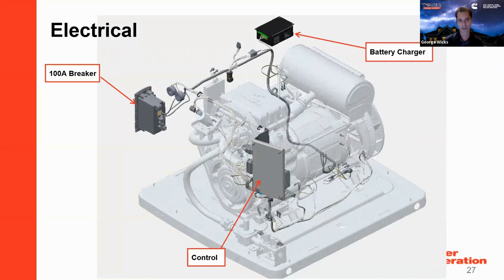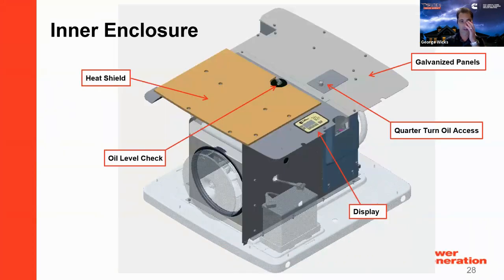In the standby gen lineup, they all come with a 100 amp breaker and a battery charger built into the generator. Different from Generac, we need a 120 volt circuit run out to our unit. Without that, the battery charger won't power and backfeed the battery, and within a month or two, the generator battery will be dead. That's one of the things installers are used to dealing with. Other brands that don't have these features onboard the generator use that 120 volt circuit to power both the battery charger and the onboard heater. It's a nice feature, but we have to have it wired up and powered.